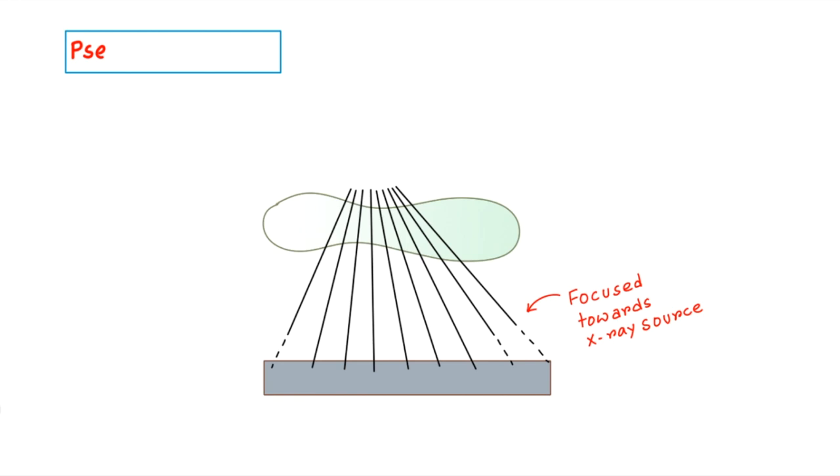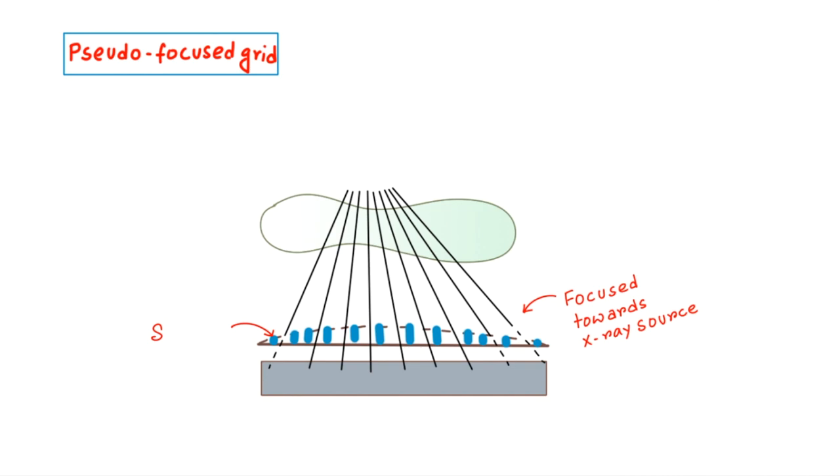Next type is pseudo-focused grid. In this type, there is progressive diminution in the height of lead strips from the center to the periphery. As the strips are shorter at the periphery, the primary photons are allowed to pass.